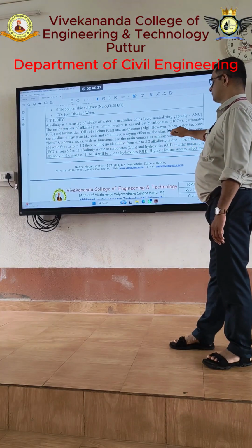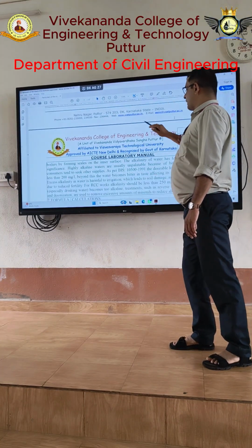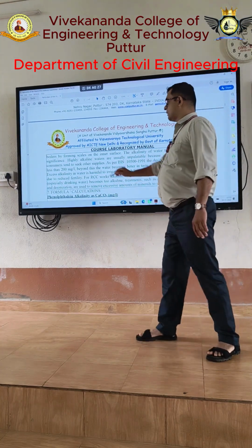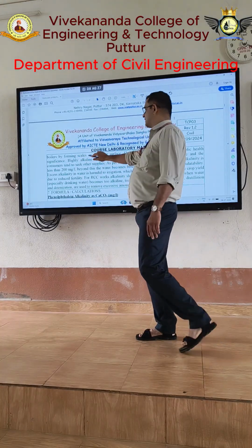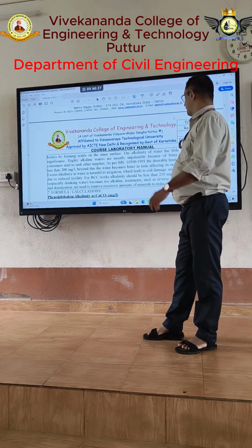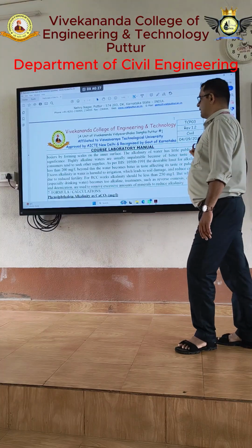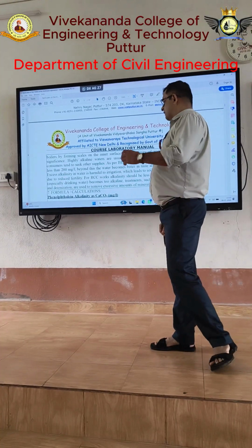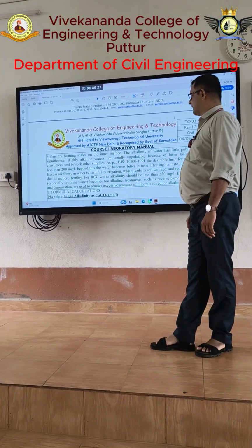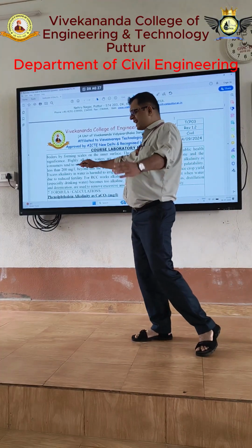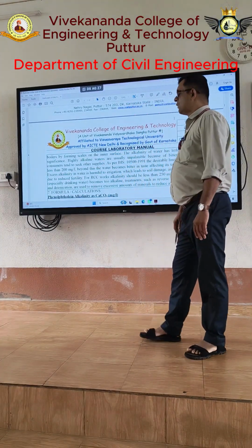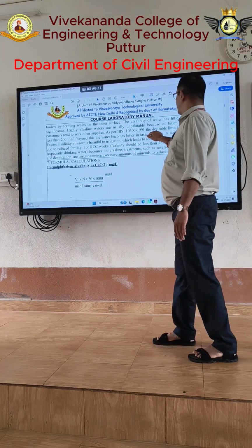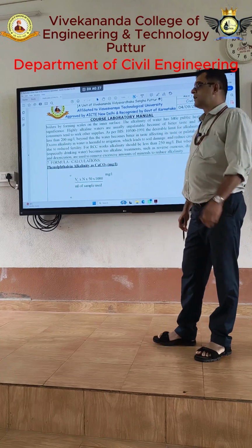Next, what are the problems when alkalinity is there in the water? The boilers used in industry start scaling on the inner surface, and it also has a small significance for public life. Then the highest value for alkalinity for drinking water should be less than 250 mg per liter or 250 ppm. Otherwise it will cause a bitter taste on our tongue.